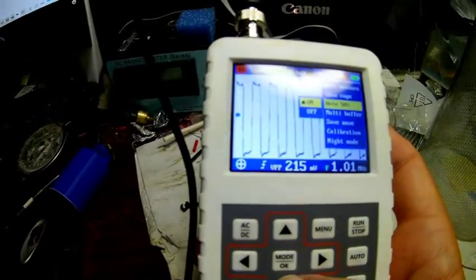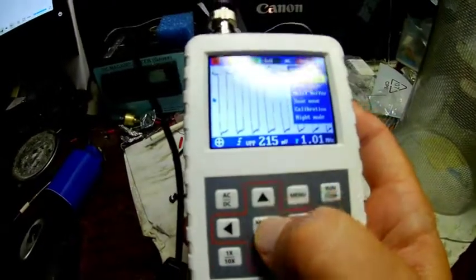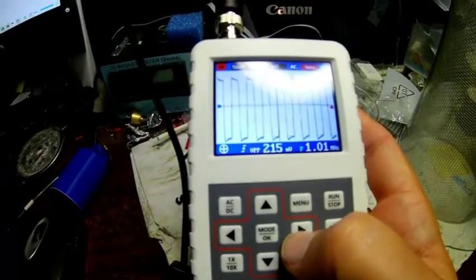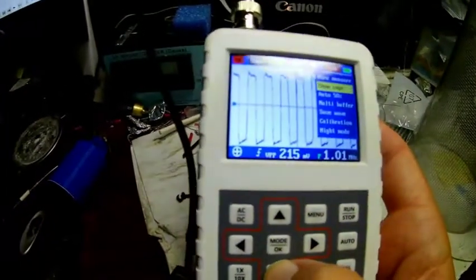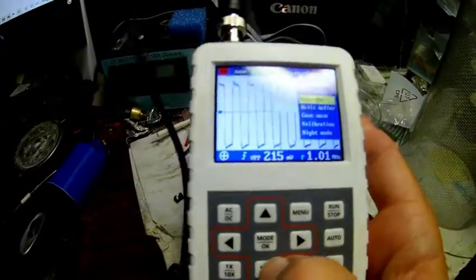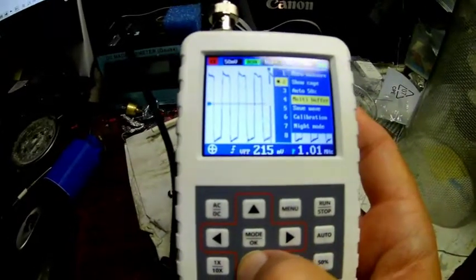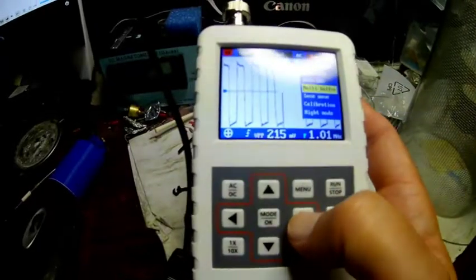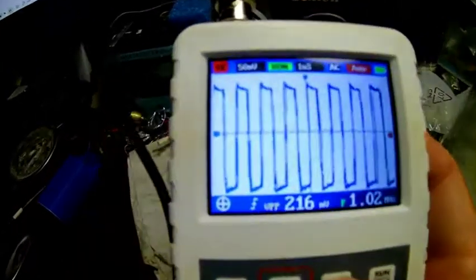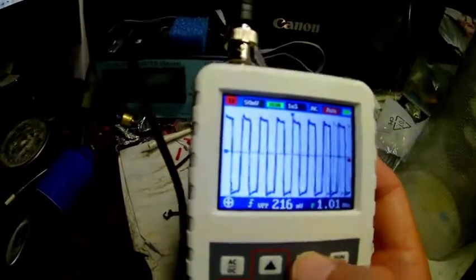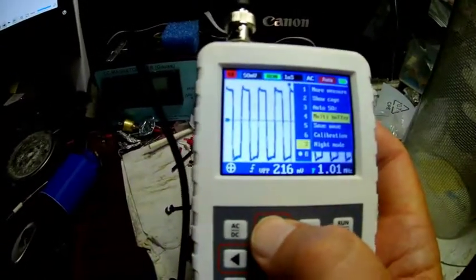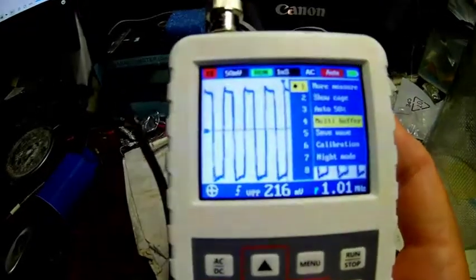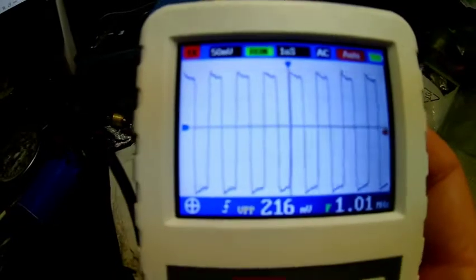Auto 50% on, what happens if we turn that off? I'm not sure what that does. Let's turn it back on I guess because who knows what that does. Multi-buffer. Let's try bringing it up to eight. Look at that, so it's got now eight overlaid traces. So that's what the multi-buffer does. And let's turn it back to one and see what happens. So now it's on one, so now it's just a single trace.